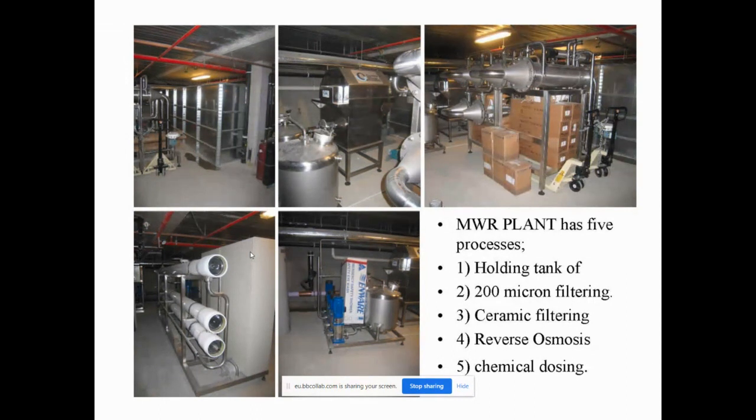And we worked on this for about three years. The guy that contracted to make the plant worked on it and actually failed to get it to work. And eventually we had to bring in someone else to do it. But I think they've got it to work now. You can take a huge amount of water out of a sewer, and it doesn't affect the flow rate of the sewer. And it's certainly worth doing. You can also withdraw heat and all sorts of things from a sewer, which is cheap. It's energy going wasted.